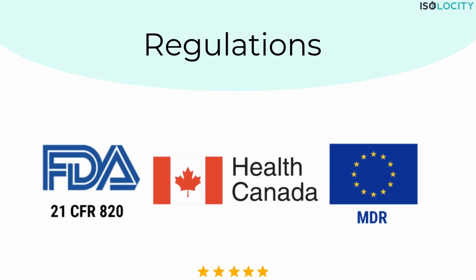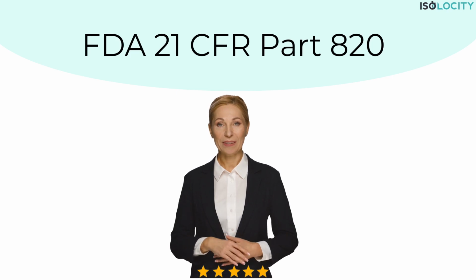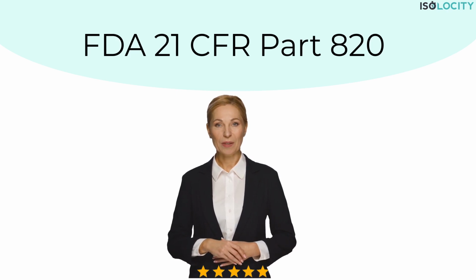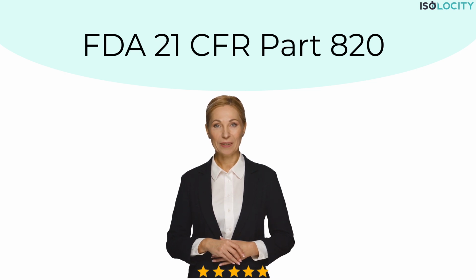ISO 13485 isn't the only standard you'll need to think about when managing complaints. There are several global and regional regulations that dictate how complaints should be handled. FDA 21 CFR Part 820. In the U.S., medical device complaints must be logged, investigated, and reported to the FDA in certain circumstances. EU MDR, Medical Device Regulation in Europe. The MDR mandates that manufacturers have a formal complaint handling process and report certain complaints to the regulatory authorities. Health Canada. Canadian regulations require that all complaints related to medical device safety or efficacy be properly recorded and reported.